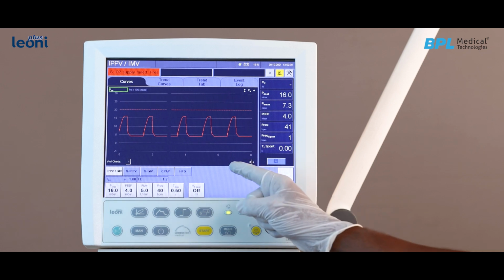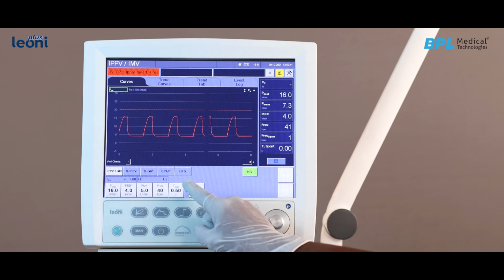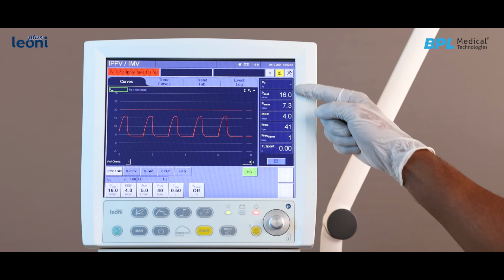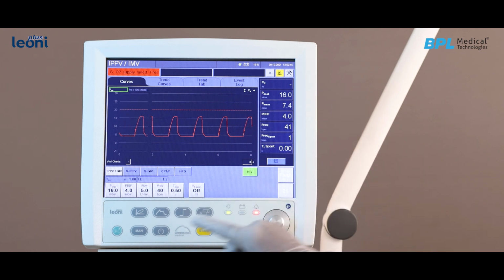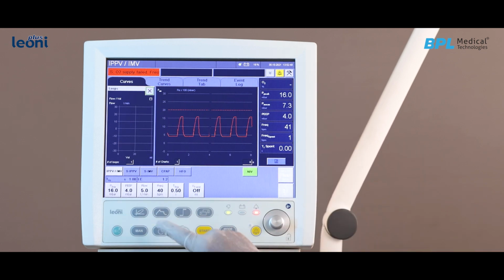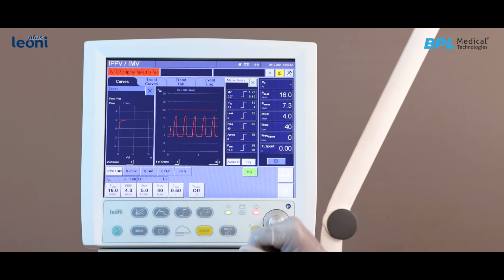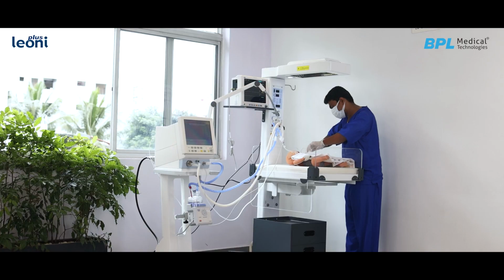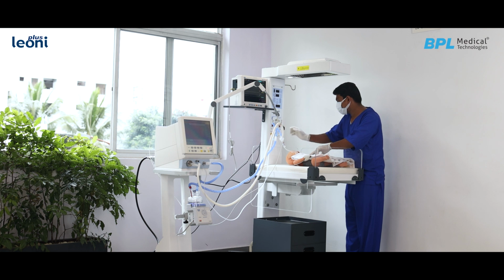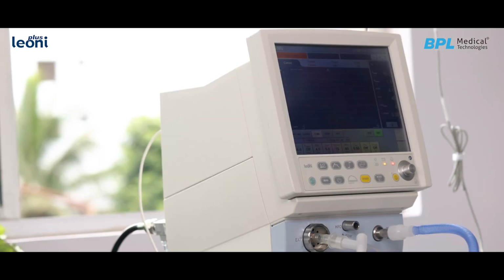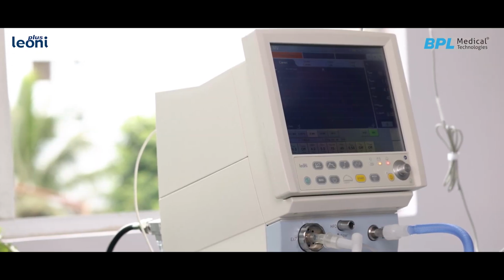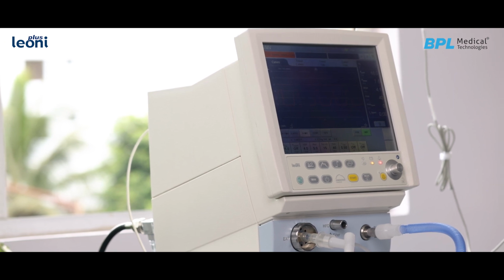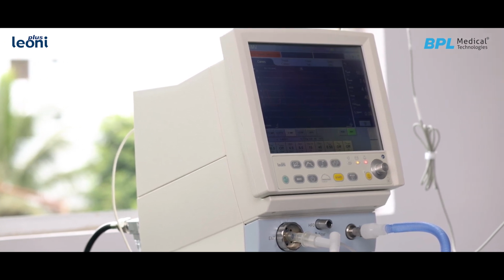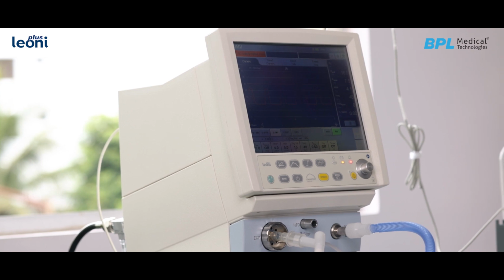With its state-of-art 12-inch touchscreen, Leoni Plus HFO enables wider viewability of patient analytics. The agile user interface with instant view technology gives an intuitive grasp of patient situation, trends, and necessary interventions. A unique double-membrane HFO technology enables active inspiration and active expiration. An inbuilt battery backup for 200 minutes in conventional mode and 60 minutes in high-frequency modes ensures better patient care during critical ventilation procedures.